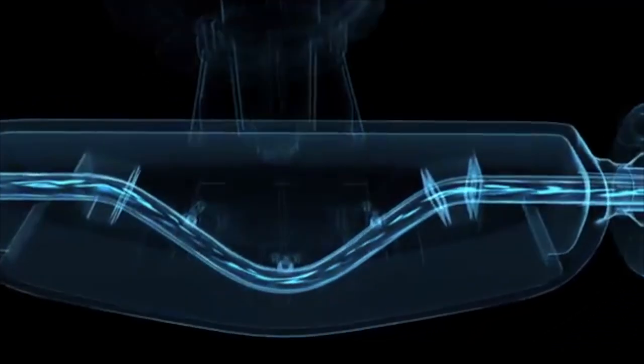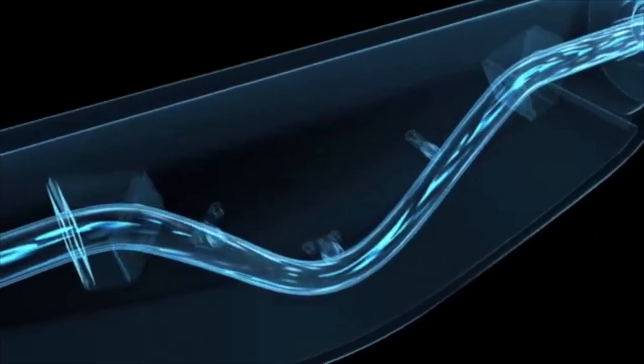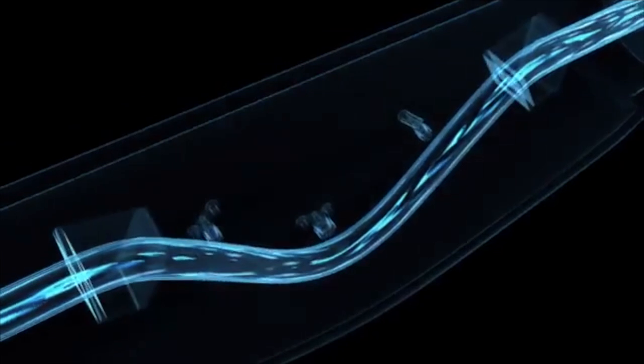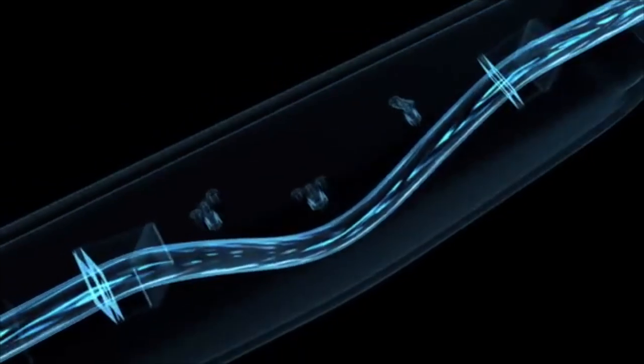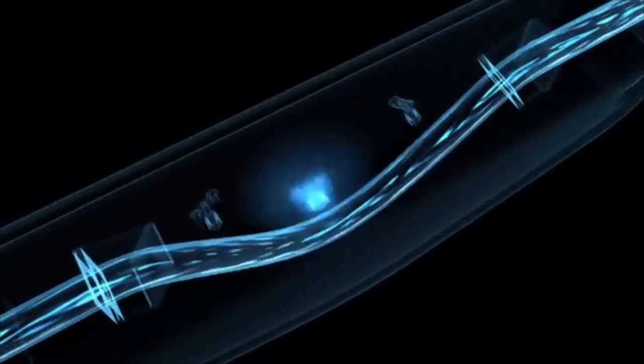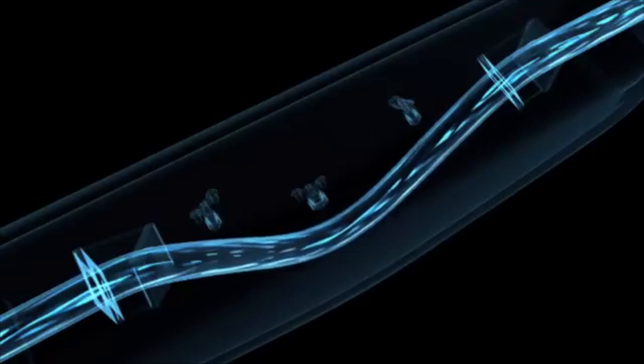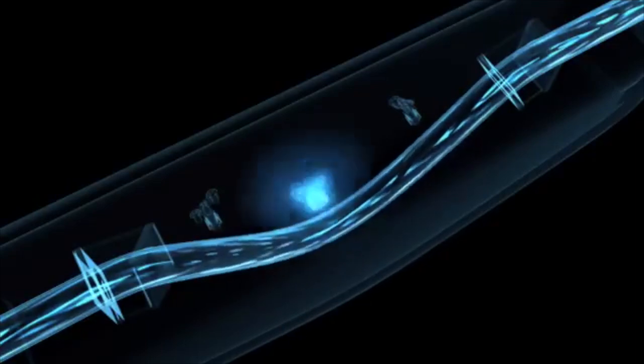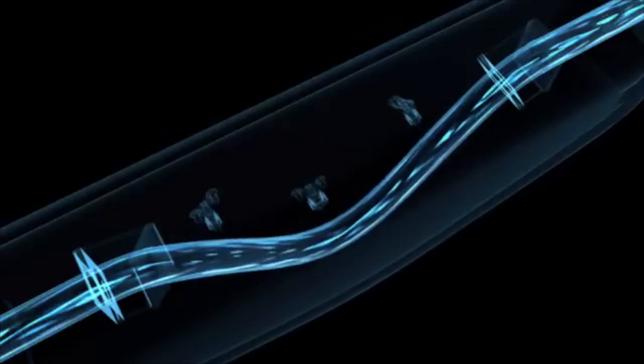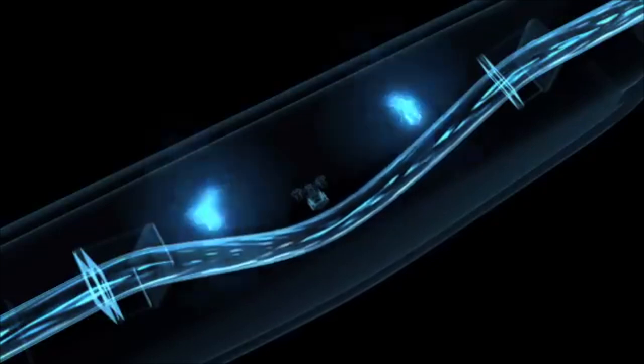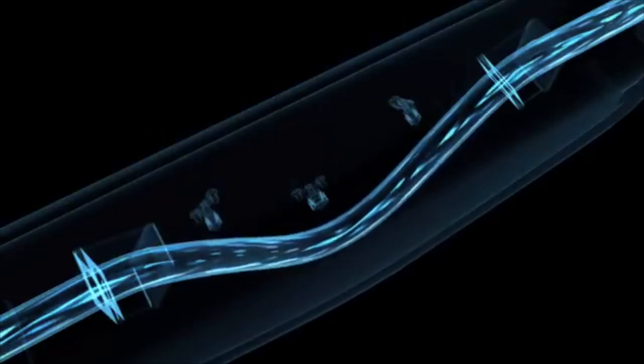A tube is located inside each Coriolis flowmeter. An exciter causes the tube to oscillate constantly. Here, in an exaggerated example, if there is no flow, the measuring tube oscillates uniformly. Sensors are located at the inlet and outlet and register this basic oscillation precisely.